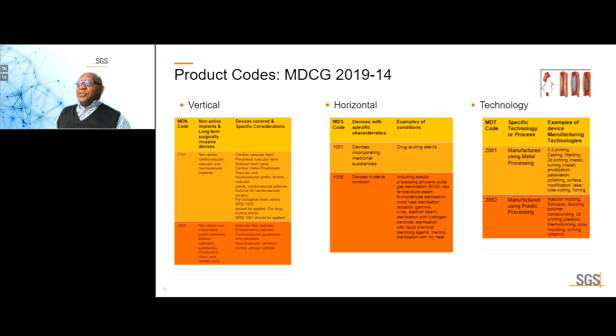As it relates to the horizontal codes, because it's a drug-eluting stent, you've got to go for MDS 1001, devices incorporating medicinal substances. So any device that incorporates a medicinal substance must have that code as well. Then, because it's going to be sold sterile, MDS 1005 would also be applicable. In terms of the technology, clearly, for the metallic component, you're going to use metal processing methods. And for the plastic components, you're going to use plastic processing methods such as injection molding, extrusion, blending, bonding of polymers, etc. So that kind of gives you an idea of how these product codes work. And this will be required when you make your application to your notified body.